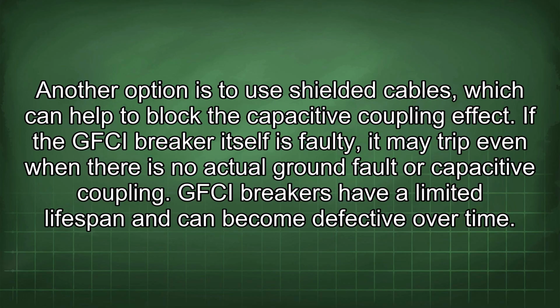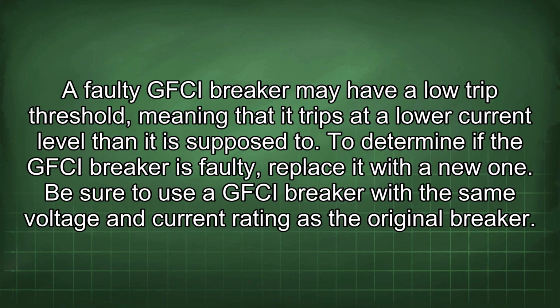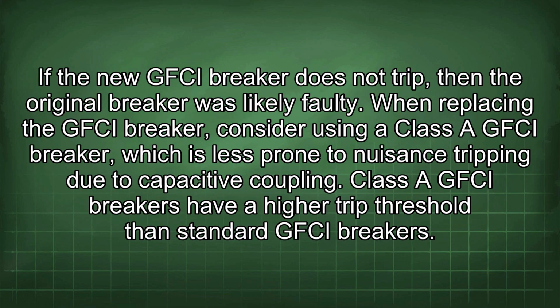If the GFCI breaker itself is faulty, it may trip even when there is no actual ground fault or capacitive coupling. GFCI breakers have a limited lifespan and can become defective over time. A faulty GFCI breaker may have a low trip threshold, meaning that it trips at a lower current level than it is supposed to. To determine if the GFCI breaker is faulty, replace it with a new one. Be sure to use the GFCI breaker with the same voltage and current rating as the original breaker. If the new GFCI breaker does not trip, then the original breaker was likely faulty. When replacing the GFCI breaker, consider using a class A GFCI breaker, which is less prone to nuisance tripping due to capacitive coupling.